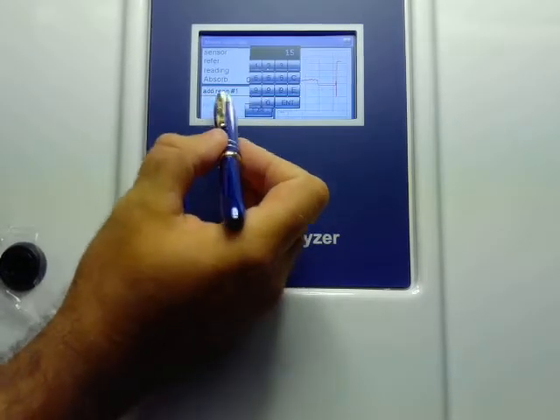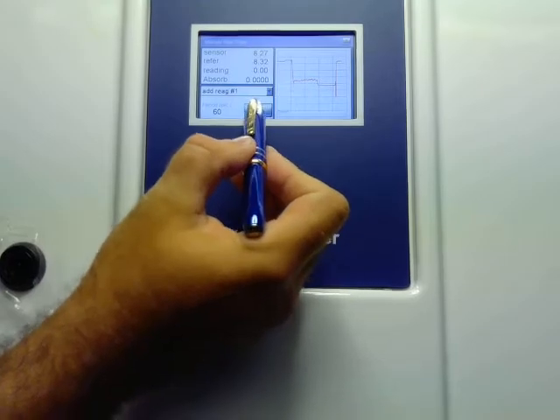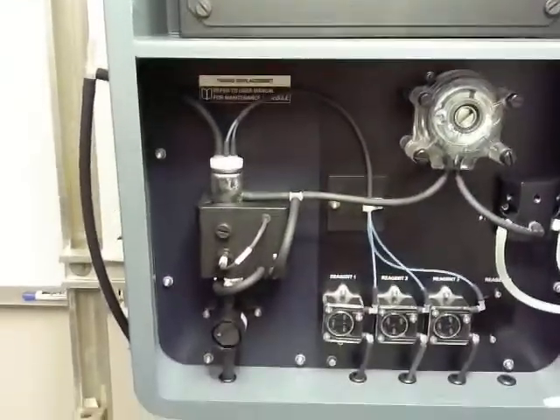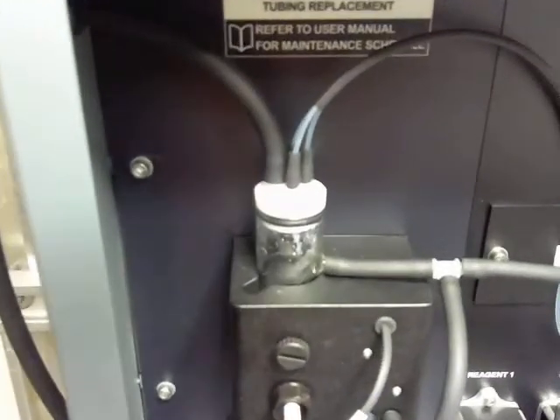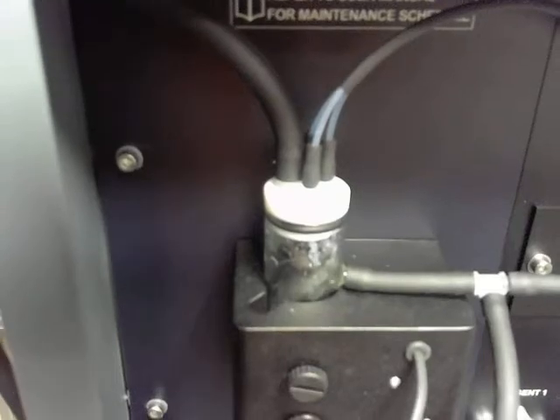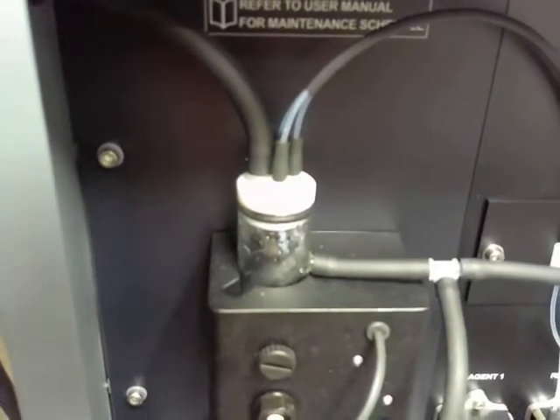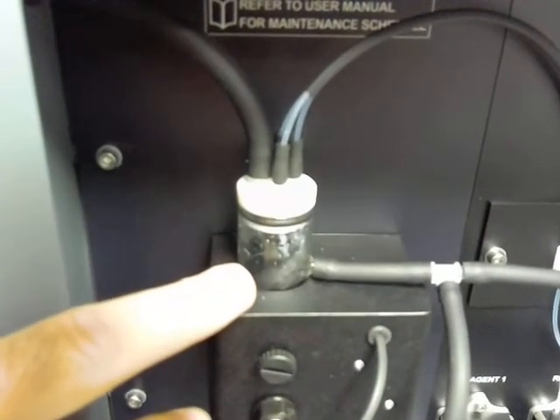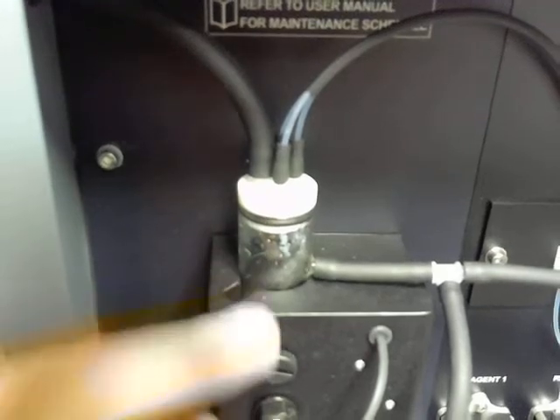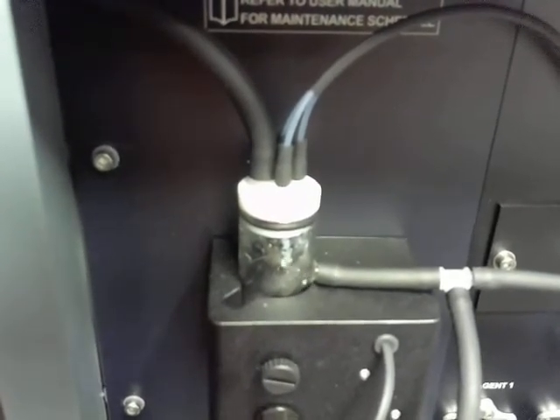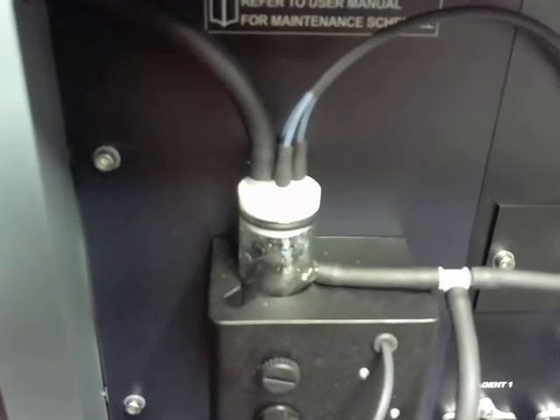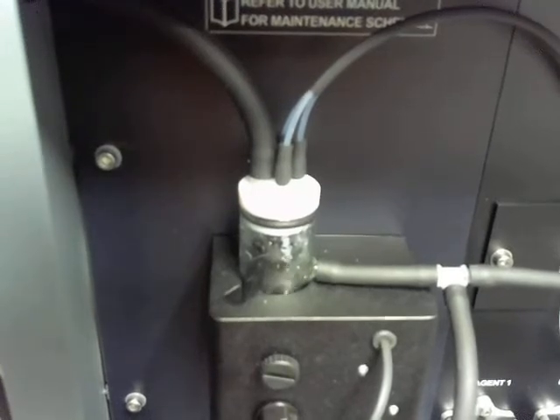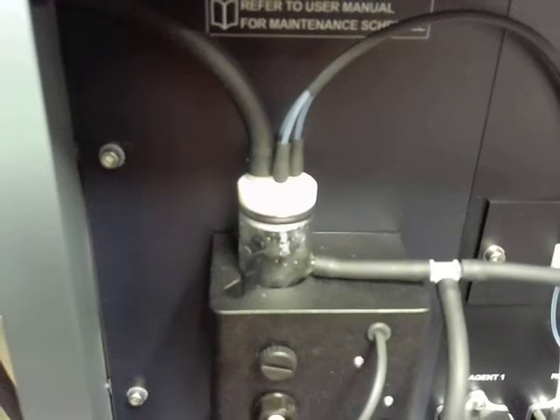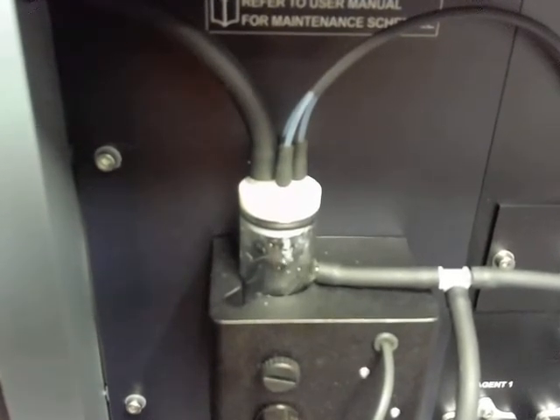So we'll go down our menu to find add reagent 1, and we'll change our timing to 60 seconds. And then we'll hit on. Now we'll hear our reagent pump start to turn. If we get real close, we want to make sure that we can actually see the droplets of reagent coming from this tube into our flow cell. That'll be a good indication that we've primed our lines. There we go. Once we see that, we know that the line is primed. And again, 60 seconds is the time that'll flush it a little bit and should get your reagent flowing nicely.